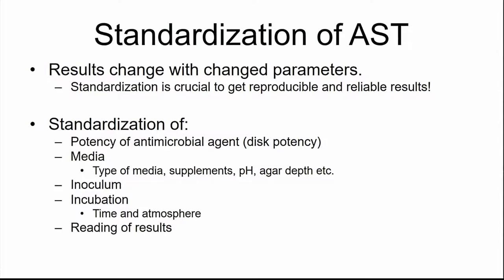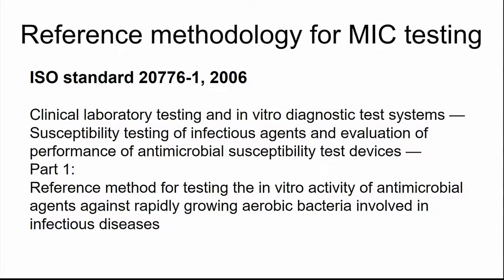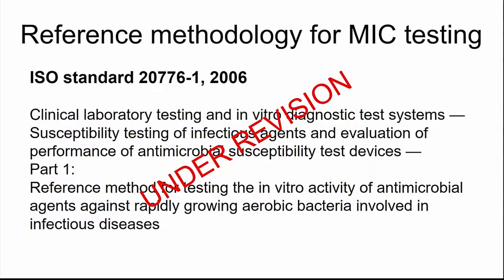The gold standard for antimicrobial susceptibility testing is broth microdilution MIC testing. There is an international standard on this that we have agreed on. The standard covers rapidly growing aerobic bacteria, so it doesn't cover everything we test. This standard is currently under revision, and a revised version will be published next year. The major differences will be that it will be more generic — for example, QC ranges currently included will be removed, and the standard will refer to CLSI and EUCAST's latest guidelines instead.